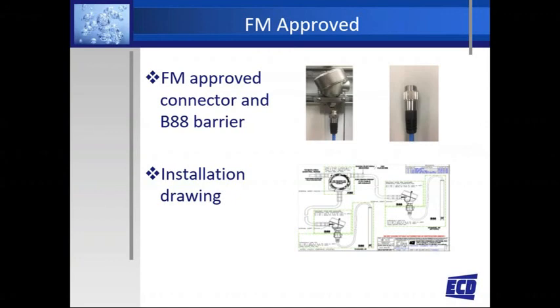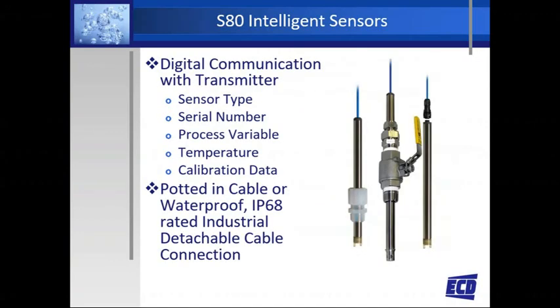The S80 sensors, which we'll get into in more detail a little bit later in this presentation, use digital communication. So between the sensor and the transmitter, we're digitally communicating instead of just millivolts, making them less susceptible to noise and interference. It also allows us to put a microprocessor in the sensor, which stores the sensor type, the serial number, process variable, and calibration data.